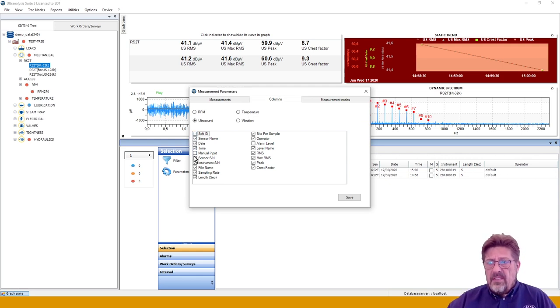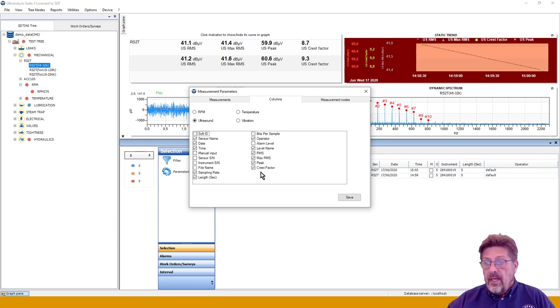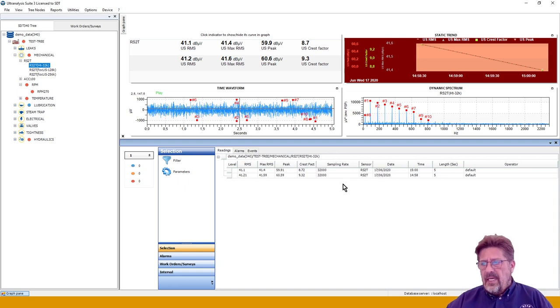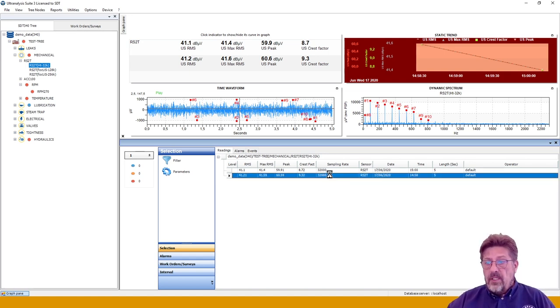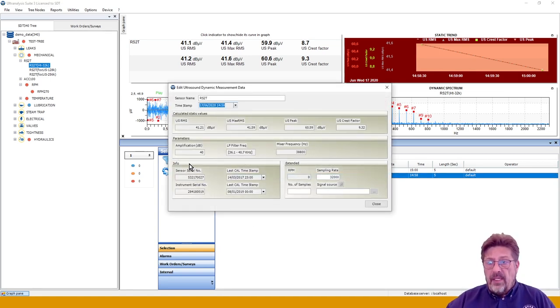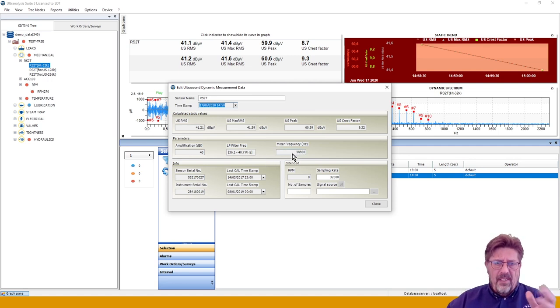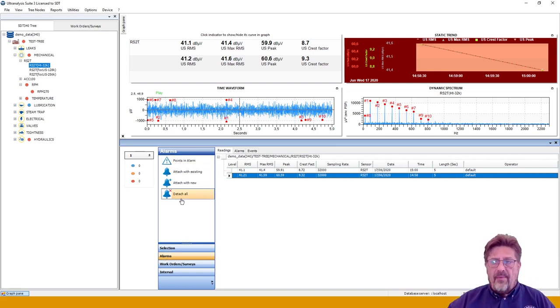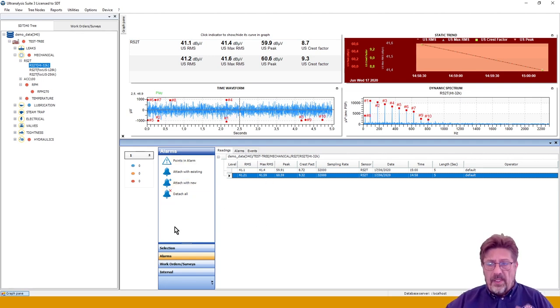If you click Edit on a measurement row, you can see sensor serial number, calibration of that sensor, instrument calibration, mixer frequency, and all that data — in case you need it, open it up and you'll see it, but you don't need to look at it every day. That's about Selection. Next is Alarms — this will be discussed very deeply in the alarms section; here you have all the commands you need for alarms. Work Orders or Surveys: you can manage your work orders from here. Using Add to Existing or Add to New, combined with the filter function: if I filter all my data and show just steam traps, then select them all using Shift, and say Add to New, I'm creating a work order with the points I just selected — I can call it 'Steam Traps Inspection.' Within two steps, the work order is created with all those points completely separately from the tree structure.